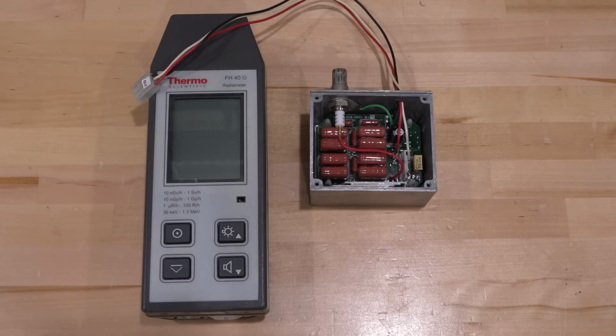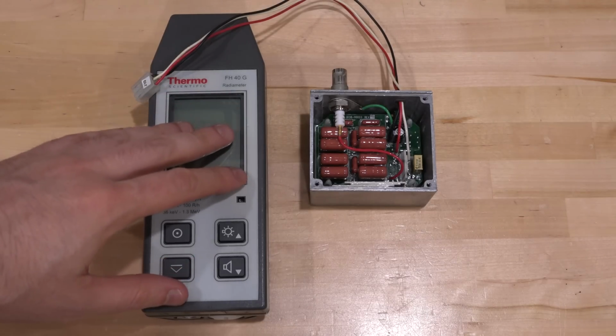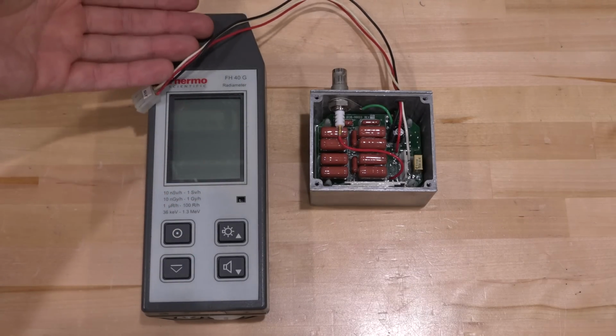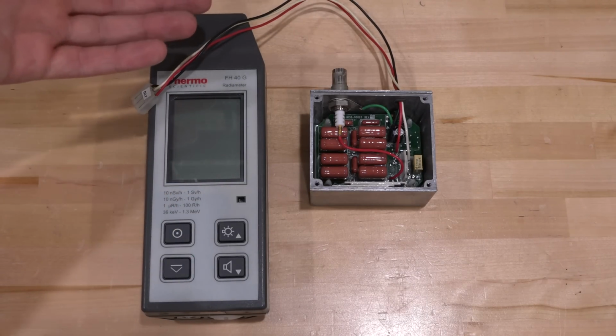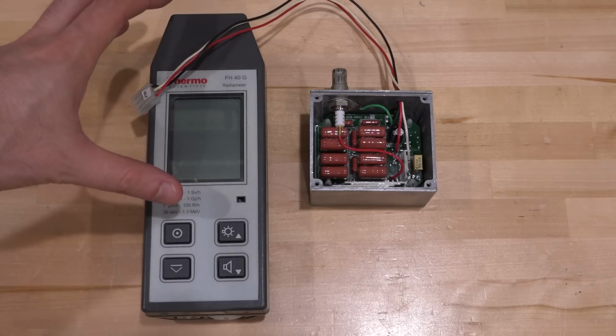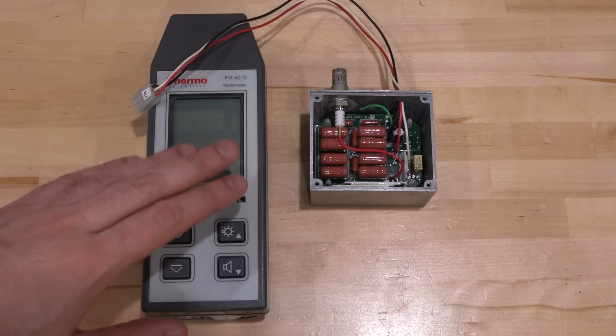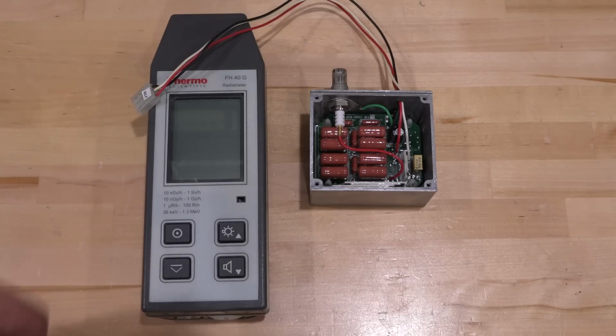But that's actually pretty easy to verify because I can place a radiometer inside of the chamber, and the radiometer will tell me if an X-ray source is coming out of the tube. And both the shutter and the X-ray source seem to be working. I could detect the presence of X-ray using this without any issues. Now, another reason why we would be getting no pulses would be if the tube is not biased or the tube is broken, the detector tube I'm talking about.